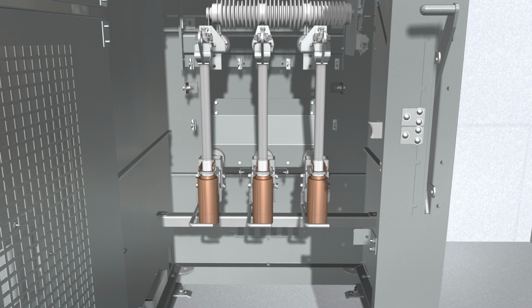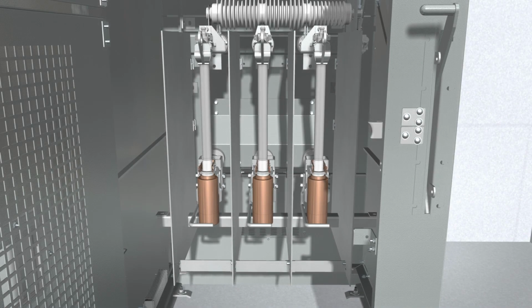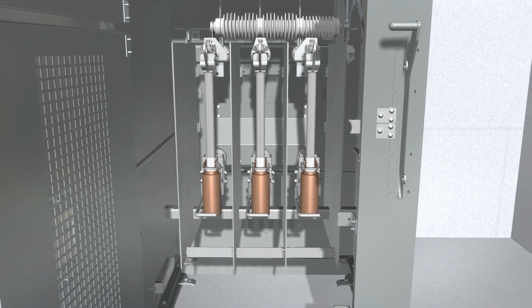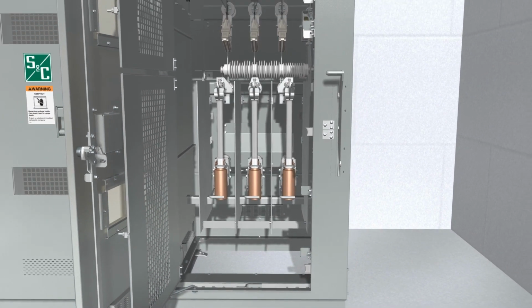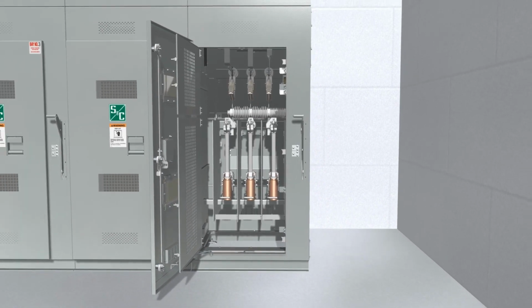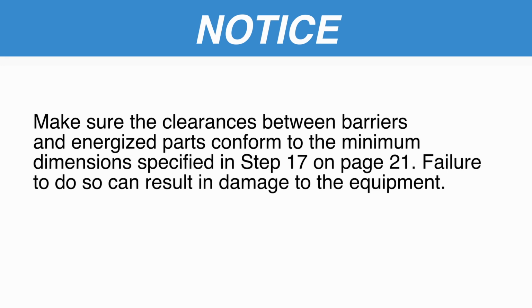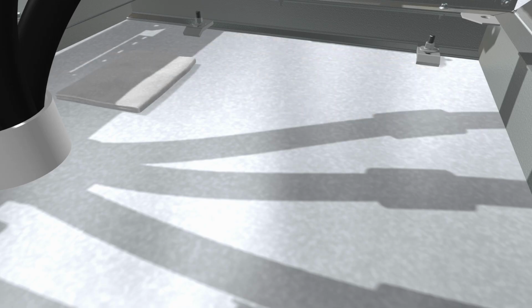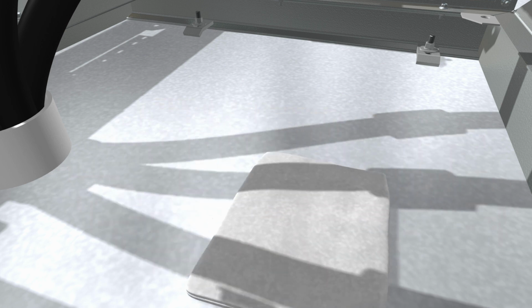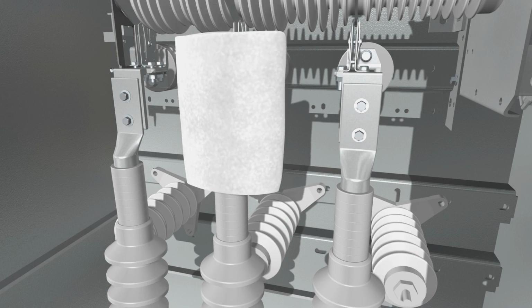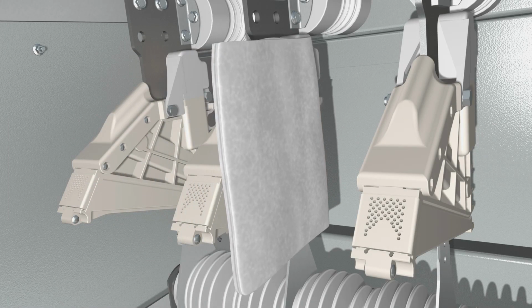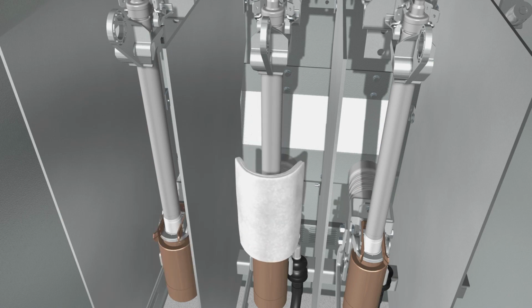Step 21. If any interphase insulating barriers were removed to facilitate accomplishment of the preceding steps, reinstall them at this time. Take care not to damage barriers on installation and make certain they are installed in the locations from which they were removed. Make sure the clearance between barriers and energized parts conform to the minimum dimensions specified in Step 17 on page 21 of the written instructions. Step 22. Sweep the enclosure floors free of debris. Wipe the barriers, insulators, bushings, terminators, switches, and fuses clean with a suitable mineral spirit solution and dry with a clean, dry cloth.